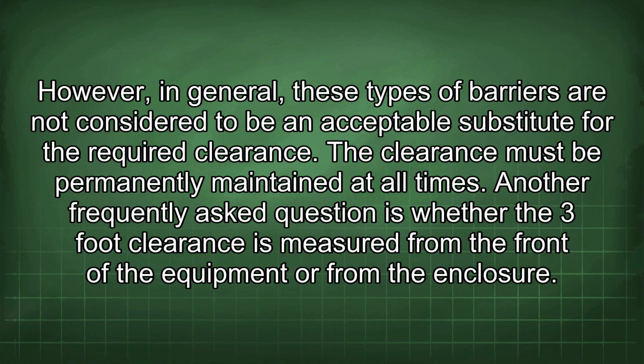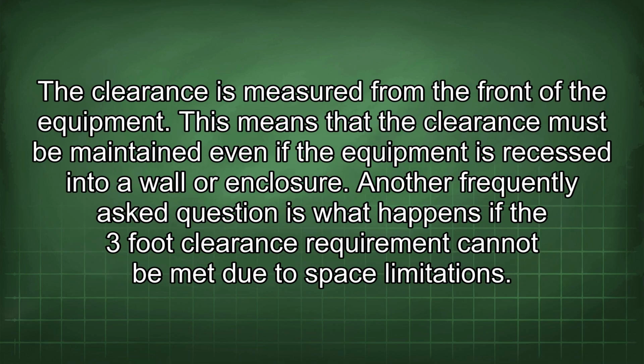Another frequently asked question is whether the 3-foot clearance is measured from the front of the equipment or from the enclosure. The clearance is measured from the front of the equipment. This means that the clearance must be maintained even if the equipment is recessed into a wall or enclosure.